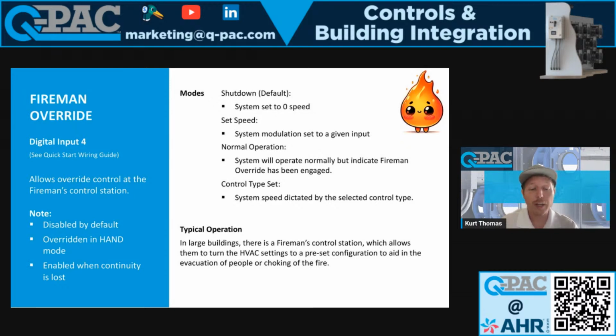So you can actually create another bypass. If you want the firemen to actually control the speed, they can give a 0 to 10 if they want. So if you want to add a relay and for us to continue to operate normally and run off of a 0 to 10, then we can do that as well. Or we can do control type set. So if you're running off of a 0 to 10 and you want us to switch control modes, say to maintain duct static pressure, then we can do that as well. So when Fireman Override is enabled, we will change the control mode to duct static pressure and make sure that we're not relying on the building automation system to maintain that duct static pressure.